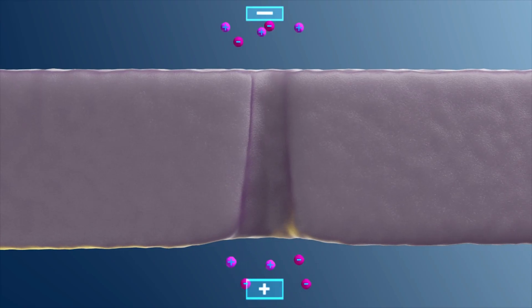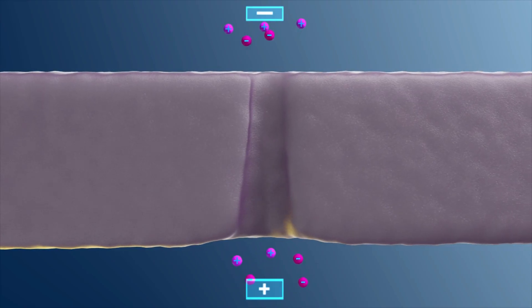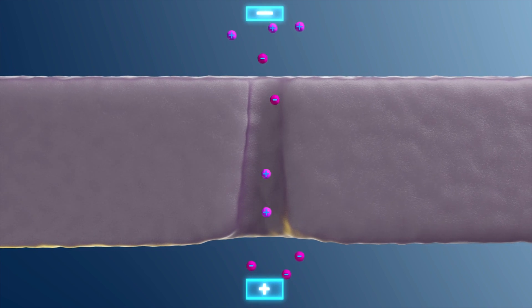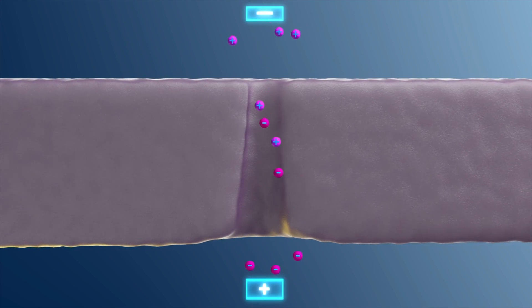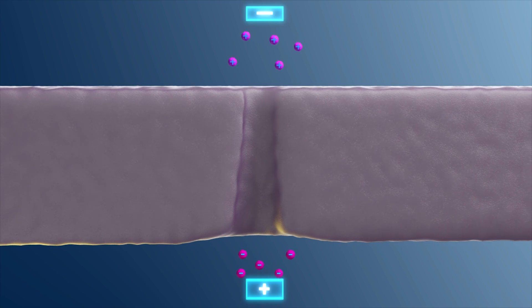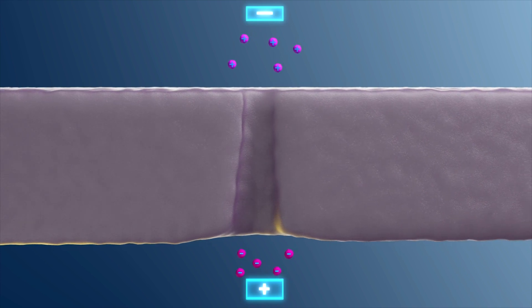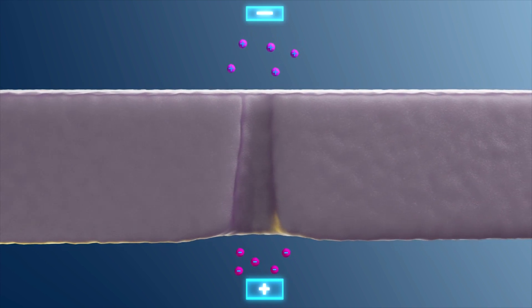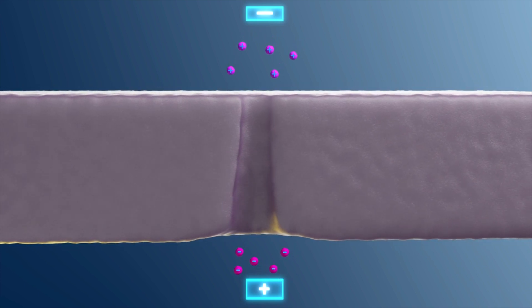Your sample must be able to be suspended in an electrolyte solution. TRPS technology uses the Coulter principle on a nanoscale. A voltage is applied across the nanopore via silver silver chloride electrodes in the fluid cell. The ions in the electrolyte solution start to migrate according to their charge in the electric field and create a stable current. We call it baseline current. The instrument records this current at a high sample rate.